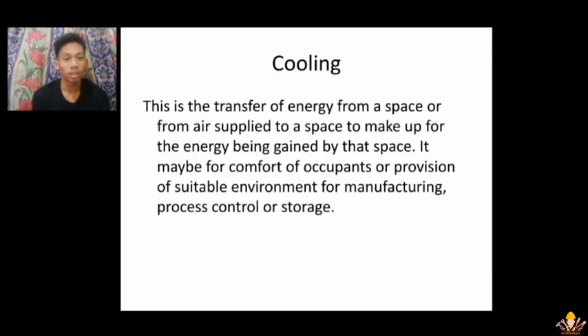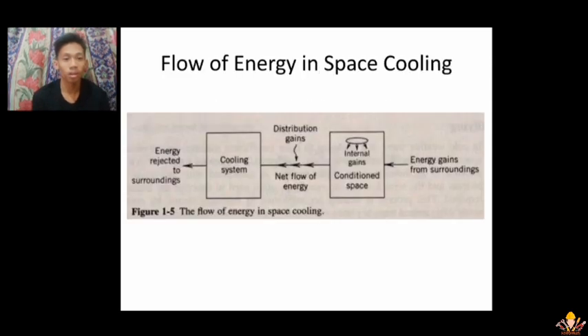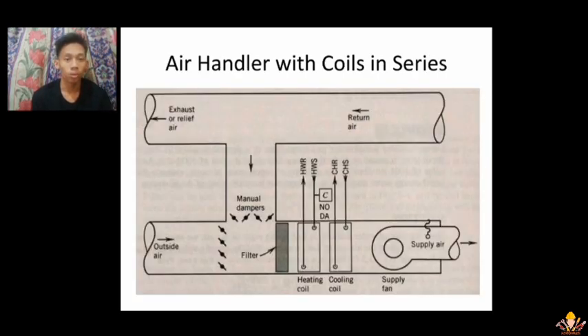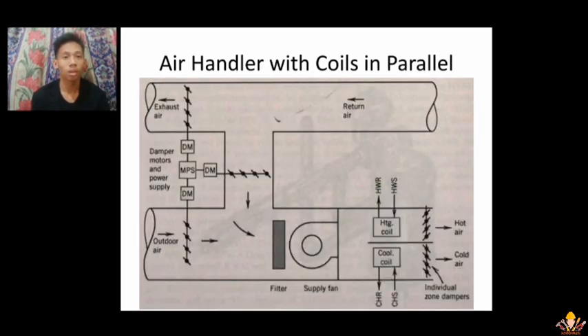Cooling. This is the transfer of energy from a space, or from air supplied to a space, to make up for the energy being gained by that space. It may be for comfort of occupants or provision of a suitable environment for manufacturing, process control, or storage. In figure 1-5, this is the flow of energy in space cooling. We have the air handler with coils in series. Also, air handler with coils in parallel.